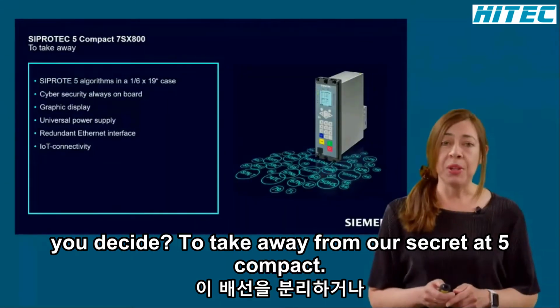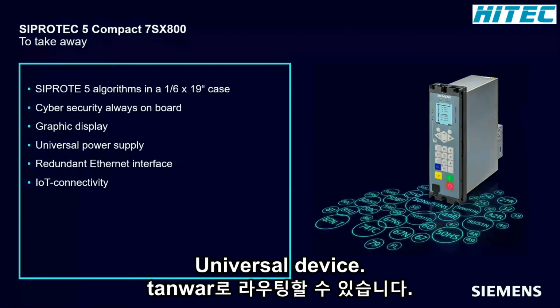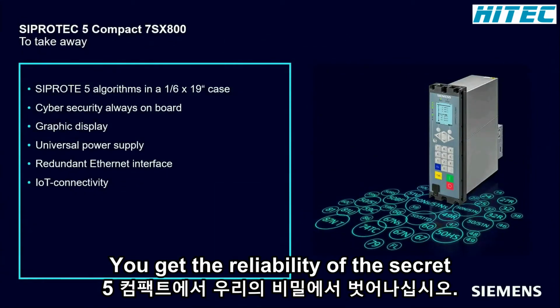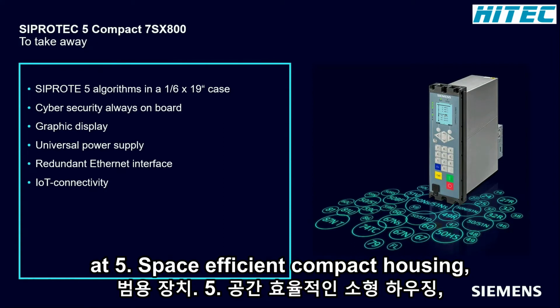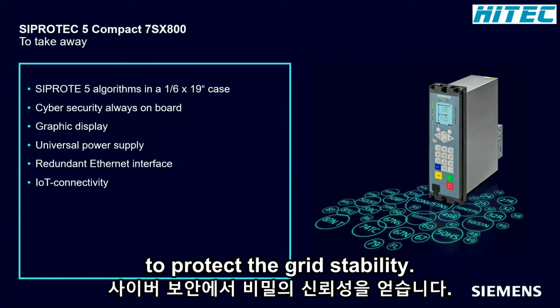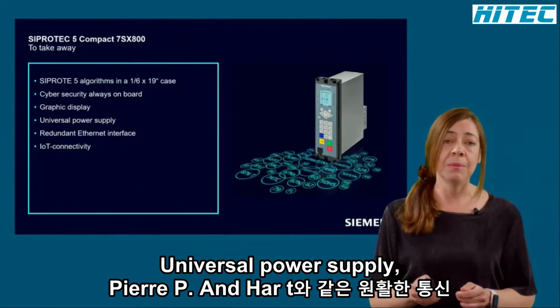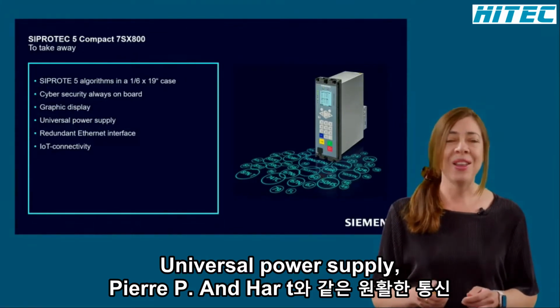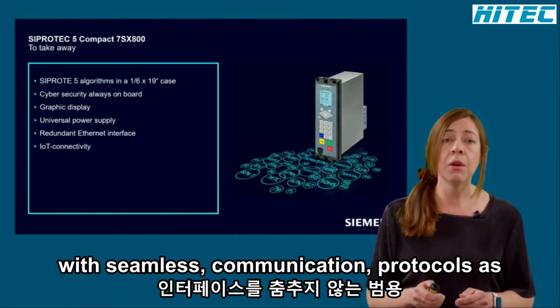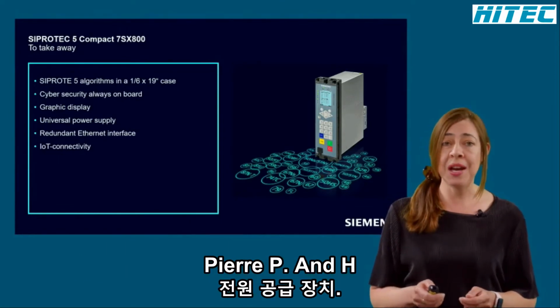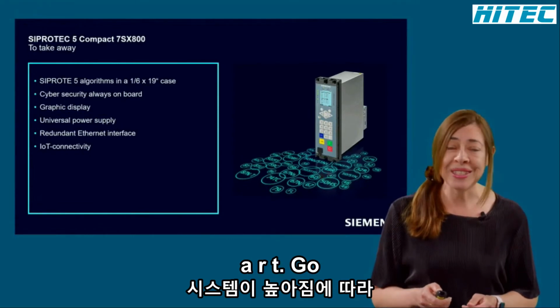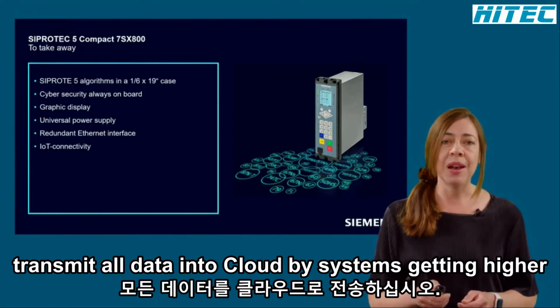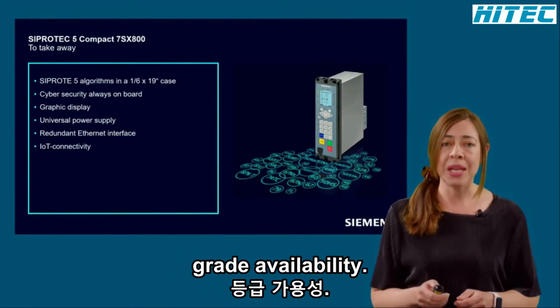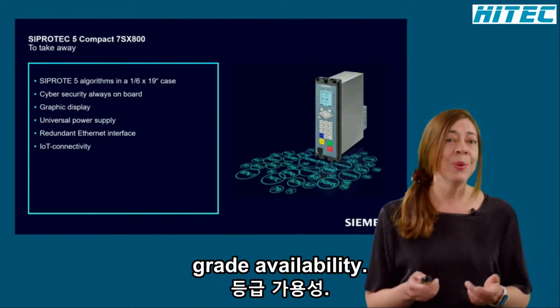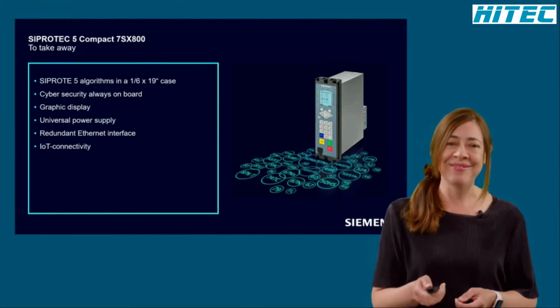To take away from our SIPROTEC 5 Compact universal device, you get the reliability of the SIPROTEC 5 algorithms, space-efficient compact housing, integrated cybersecurity to protect the grid stability, graphic display, universal power supply, redundant Ethernet interface with seamless communication protocols such as PRP and HSR, and IoT connectivity to transmit all data into cloud-based systems, getting higher grid availability. Klaus will show now some applications and functions.